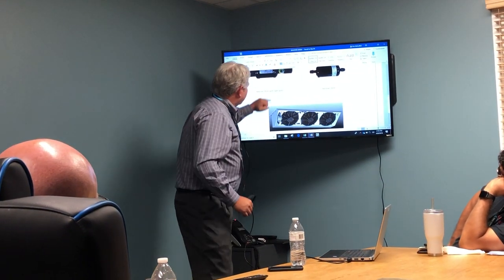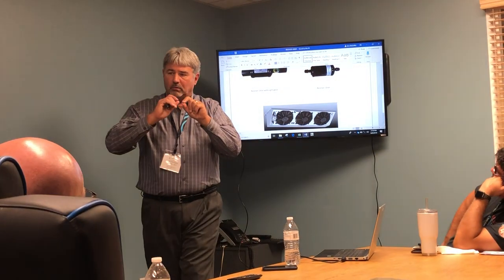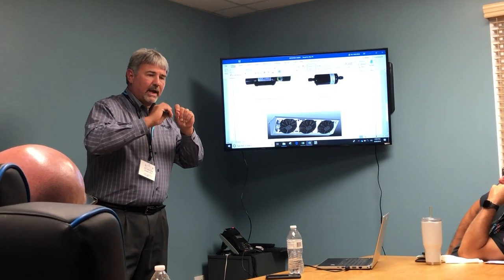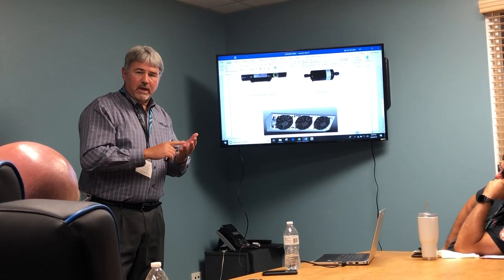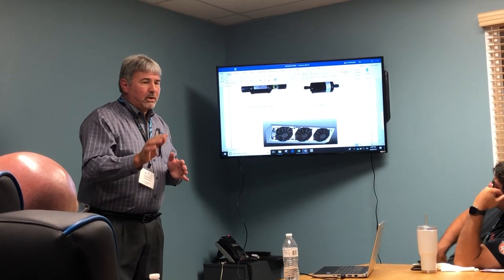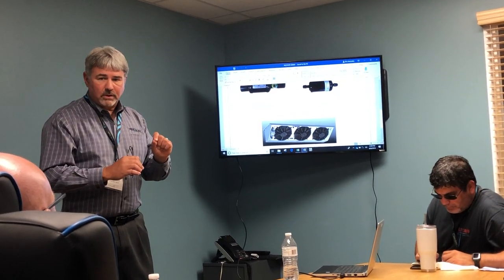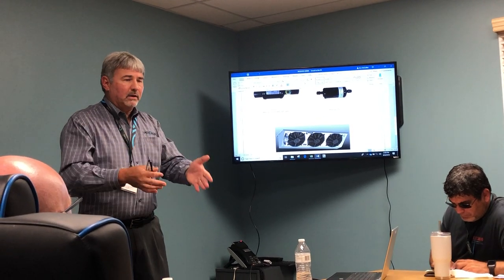And this is what I was talking about. It has a sight glass on it. And if you can see a cloudiness or milkiness in that sight glass, that means the system's not charged, or you've got some type of restriction. You've got something that's not quite right. It may be cooling and maybe just needs a little more refrigerant, but that's an indicator that there's something wrong.